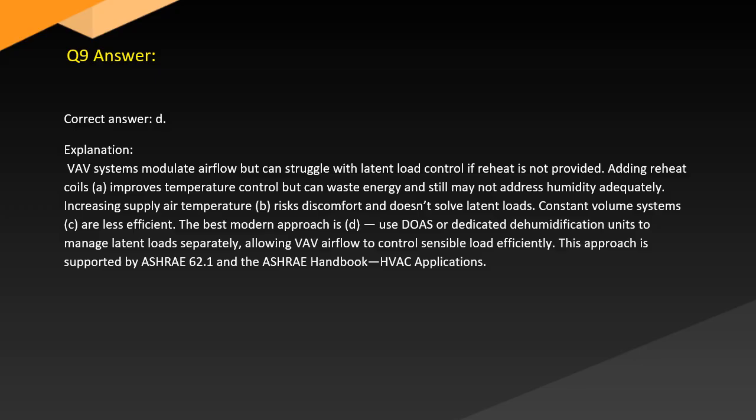The best modern approach is D. Use DOAS or dedicated dehumidification units to manage latent loads separately, allowing VAV airflow to control sensible load efficiently. This is supported by ASHRAE 62.1 and the ASHRAE Handbook, HVAC Applications.